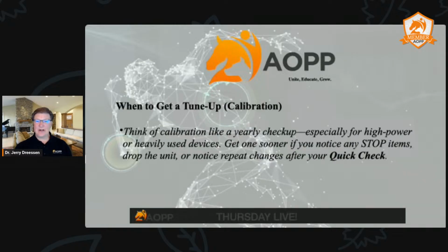Going down the list here, when to get a tune-up, when to calibrate it. Well, think of a calibration like a yearly checkup, especially for high power or heavily used devices. So if it's got a lot of hours on it every year, again, that's your baby. If it's going to go down because it wasn't maintained, it's going to be a lot more expensive. Get one sooner if you notice any of our stop items, or if the unit gets dropped, or if you notice a repeat change after your quick check. So that's our advice to you on keeping your device healthy.